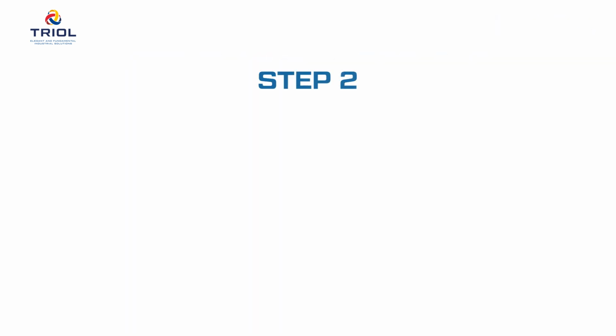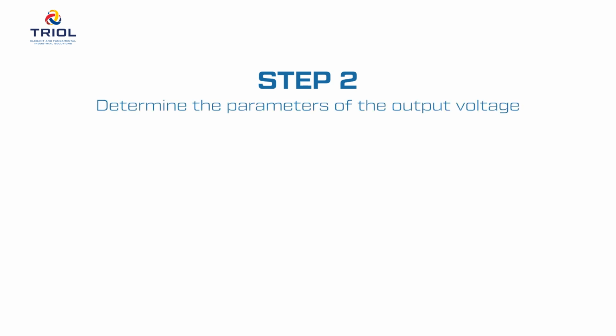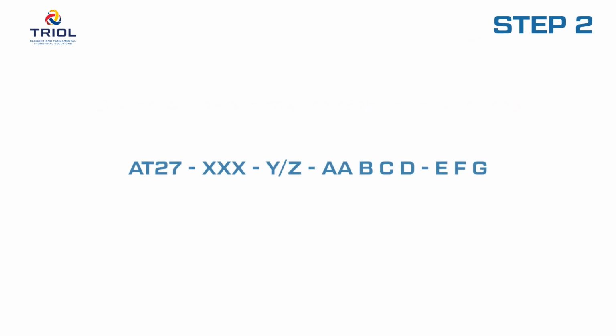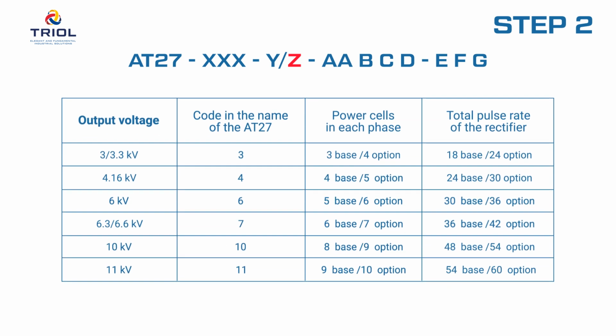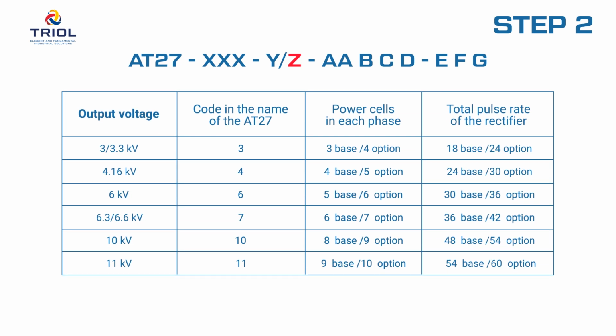The second step in forming the name of the AT27 is to determine the parameters of the output voltage. The AT27 output voltage is determined by the value of the rated voltage of the connected electric motor. For the future, it is useful to know that the output voltage of the variable frequency drive determines the number of power cells in each phase of the AT27, as well as the total pulse rate of the rectifier. We call this number of cells the base number of cells. We call the other number of the cells in a phase optional.